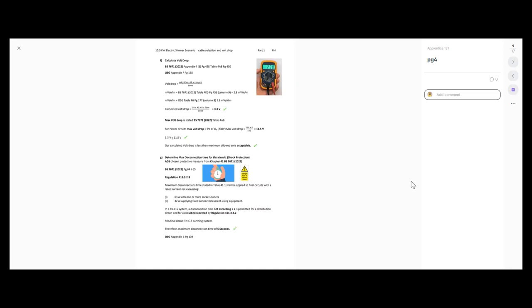We've got two options to use Table 41.1: does our circuit supply socket outlets up to 63 amps? No. Does it supply fixed current-using equipment up to 32 amps? No — because our circuit is supplying equipment above 32 amps, 50 amps. So we can't use Table 41.1. Looking under that table in a TN-CS system, a disconnection time not exceeding five seconds is permitted for a distribution circuit, or for a circuit not covered by regulation 411.3.2.2. Our circuit isn't covered by the previous regulation — therefore our maximum disconnection time for this circuit is five seconds.